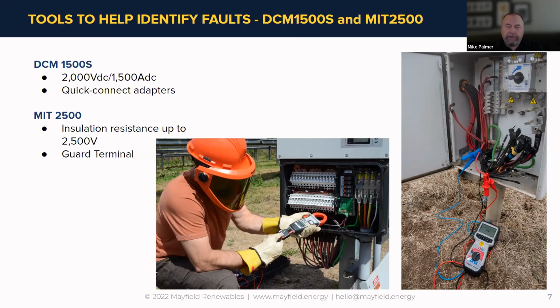Yeah, that's certainly one we get daily in the application engineering group. And we've heard it all. Obviously it's a de-energized test, so we're doing an IR test on a de-energized circuit, but with that panel sitting in there, there is a possibility, and the module manufacturers have told us that. So we just take the line of caution, and I think I answered in an email, I don't know if our viewer has gotten that yet. If you can IR test, and I know it's hard because we want to put the loop together with the modules and the cable, but if there's a way to do the testing before all that's put together, without the module in the loop, it's certainly the way to go.